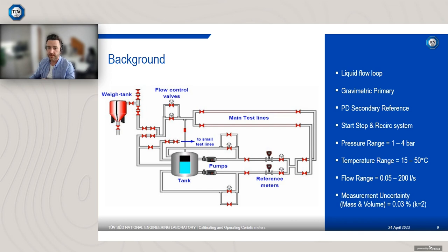So we'd flow round through the tank, from the pumps, through the test section, through the master meters, and then into the weigh tank if required. We would then compare the totalised mass or volume collected in the weigh tank against the device under test. So it could be a Coriolis meter, an ultrasonic device, a turbine meter for example. We would compare that total mass or total volume against the weigh tank.